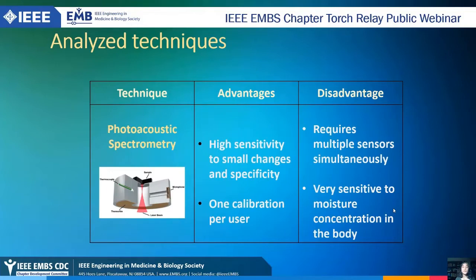Another technique is the photoacoustic spectrometry. It requires multiple sensors because it uses sound and light. The response to these variables can be associated to the glucose levels. It has the advantage of high sensitivity to small change and high specificity, and it only requires one calibration per user. However, it requires multiple sensors working simultaneously, and it's very sensitive to moisture concentration in the body.